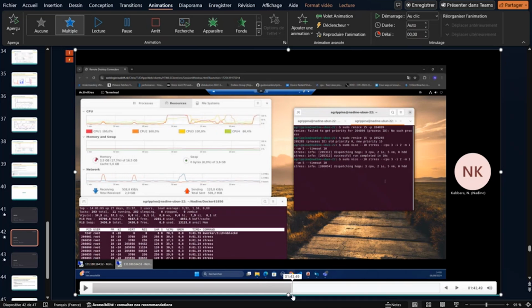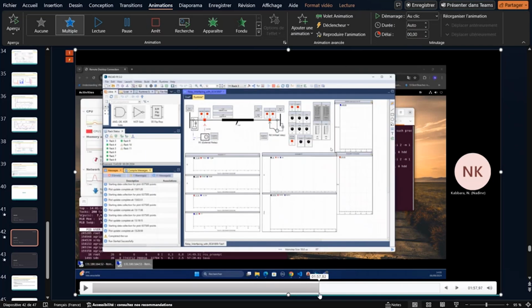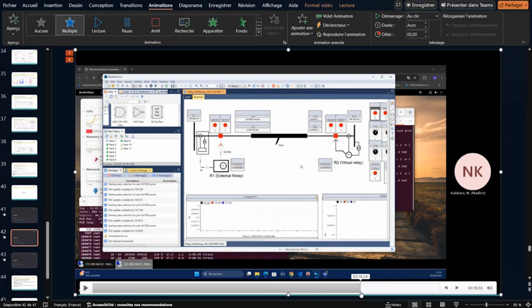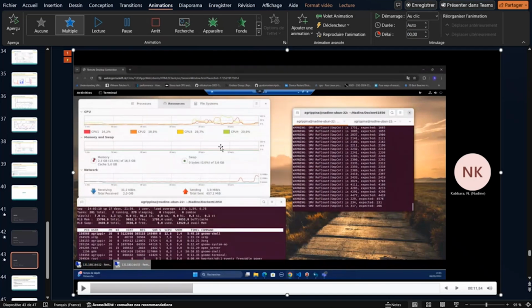And in parallel, we are running RTDS, and we can simulate a fault. Then I collect the trip signals to see if there was a delay or a drop or a latch. And the last one shows you the impact on IEC 61850. While running the resource exhaustion, the sampled value count or GOOSE count, which is usually sequential, 1, 2, 3, 4, 5, up to maybe 4,000, starts giving you warnings that it expected packet number 2000 something, but received 2200. So there's a delay of a few hundred packets that are being dropped or not even considered by the process, due to the resource exhaustion attack happening in parallel.